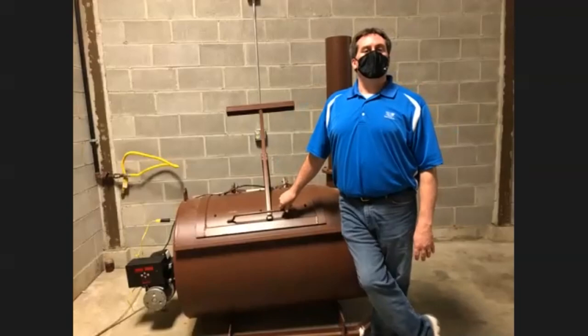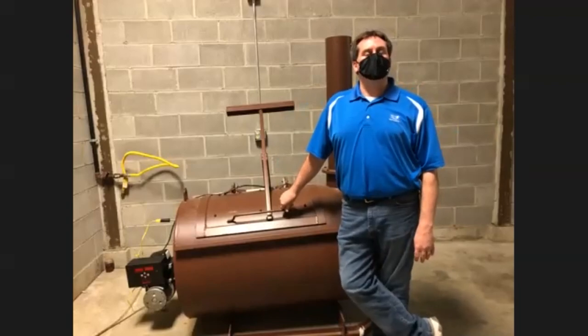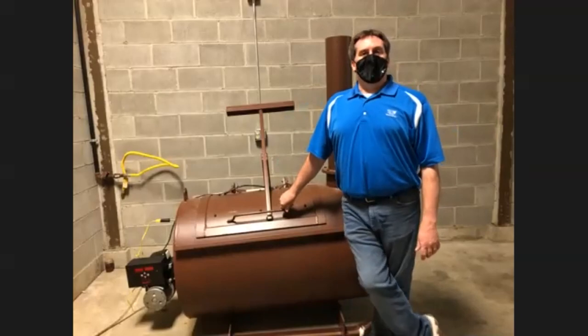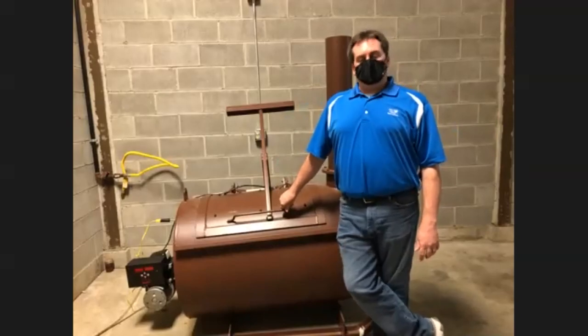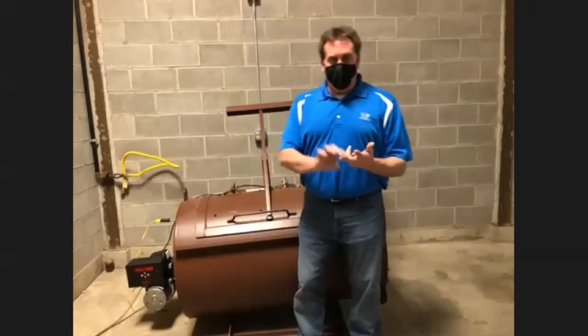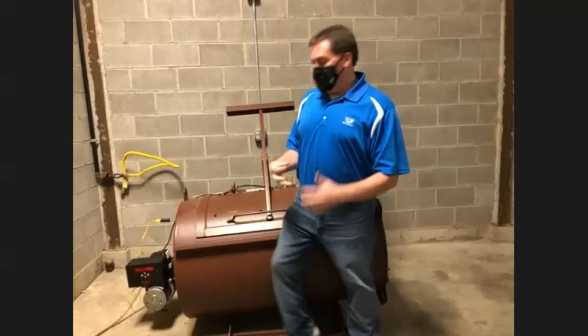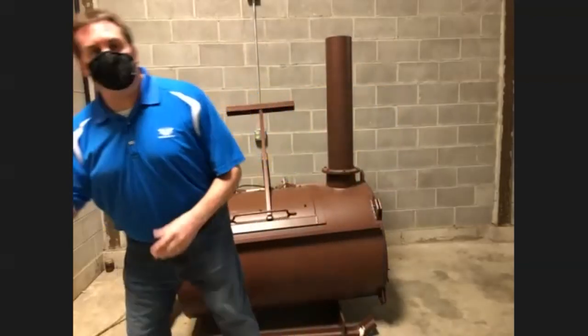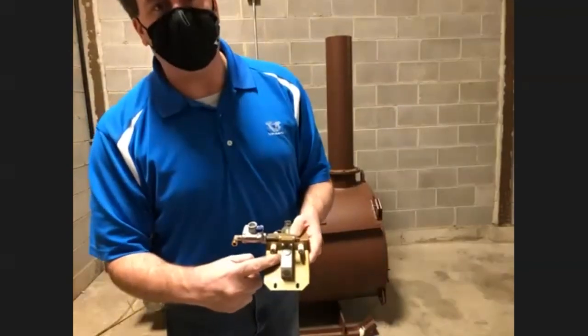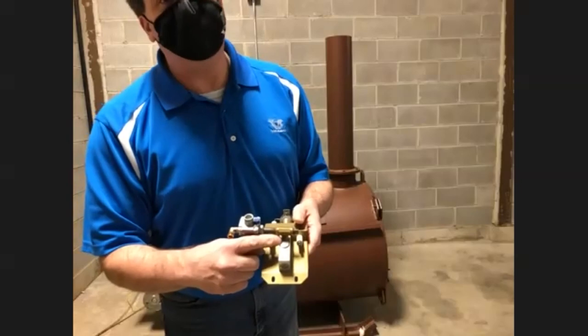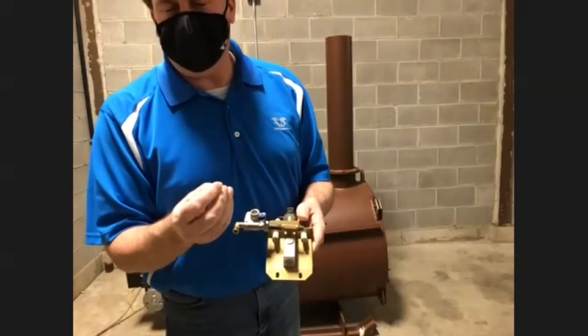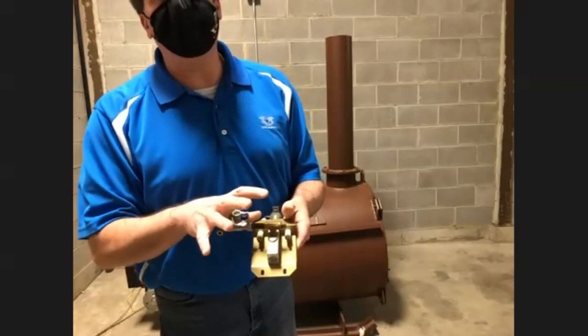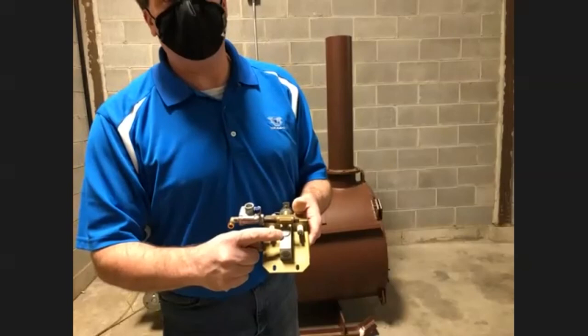I agree with you. Round is better than square. Yes. For the natural gas cremator and propane, can we use the same burner or a different burner, or can we modify propane to natural gas? You would order a natural gas burner or a propane gas burner. Really the only difference inside is an orifice inside this T-block assembly. You can convert it. I believe we do have a conversion part number for it. But typically they are the same burners. It's just an orifice inside that would need to be changed out.